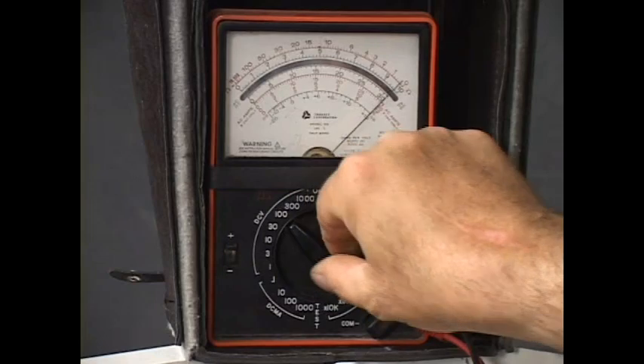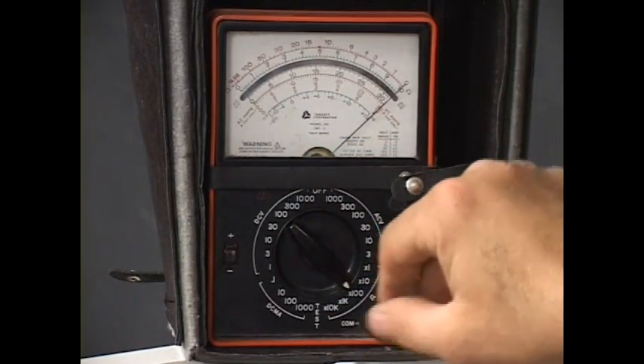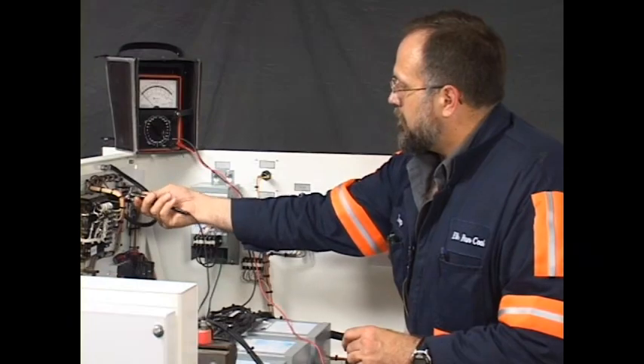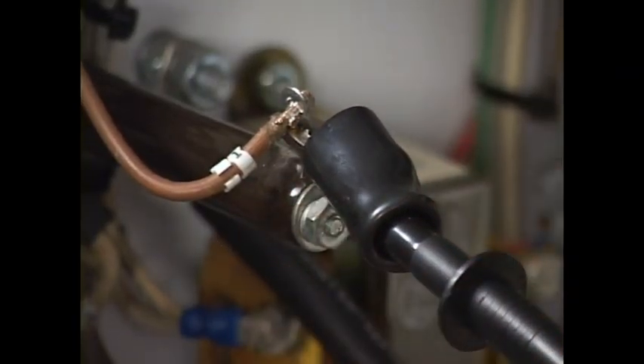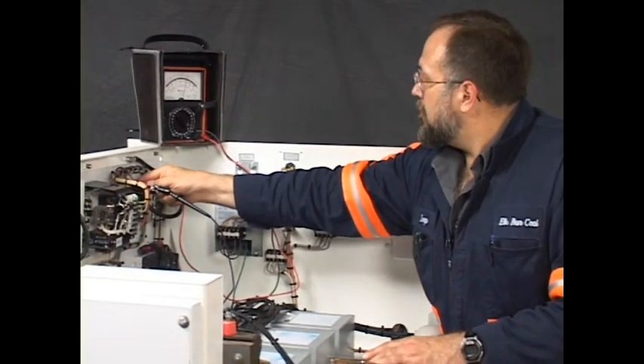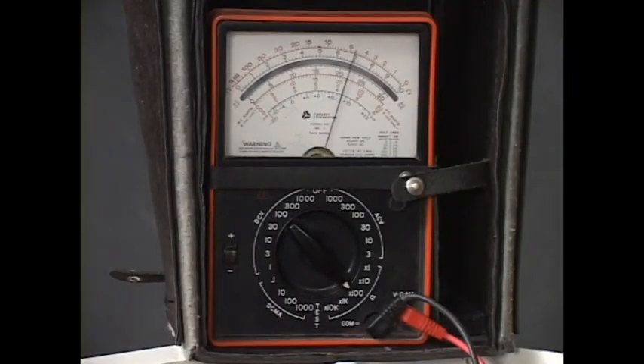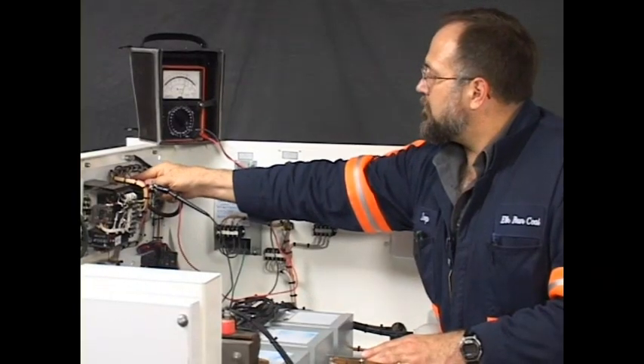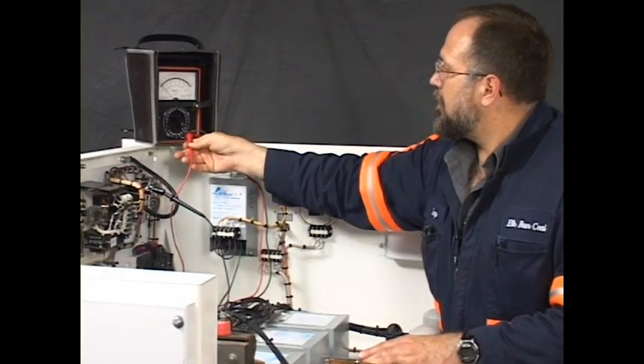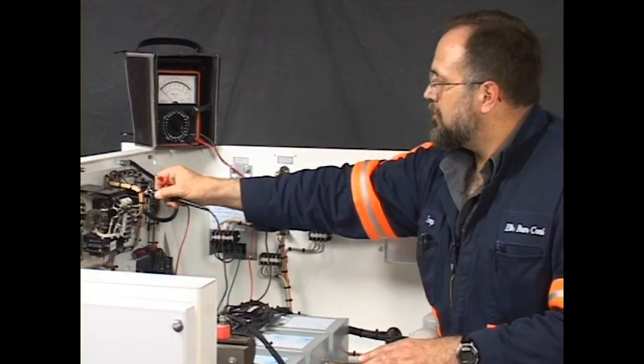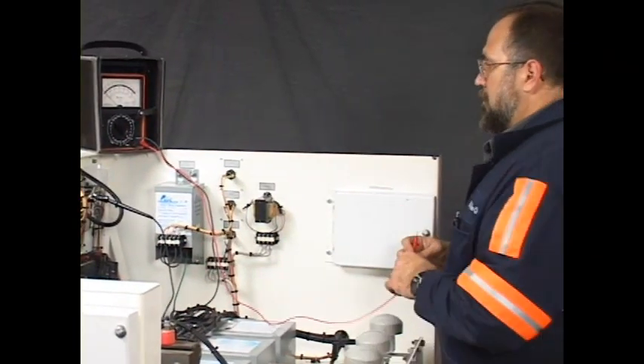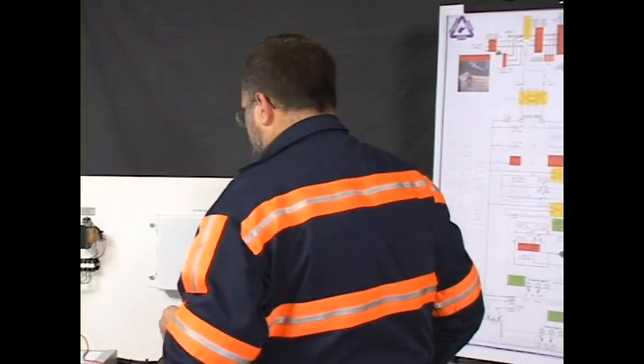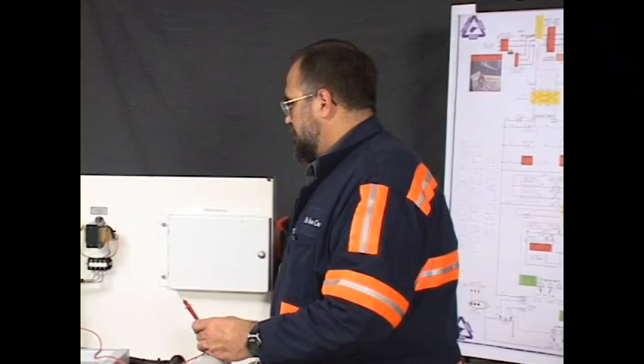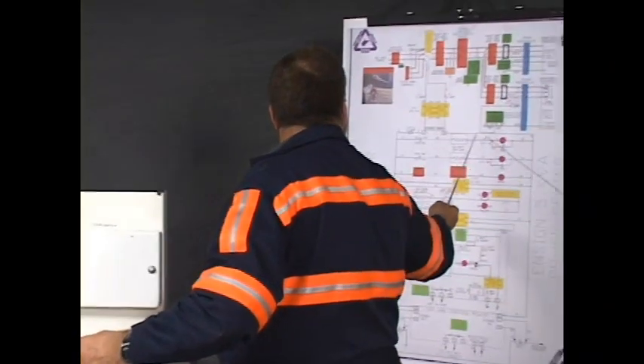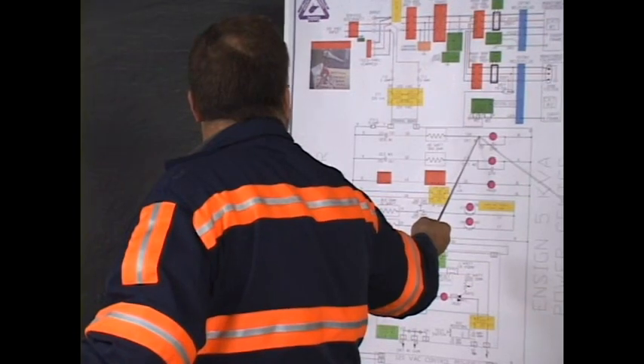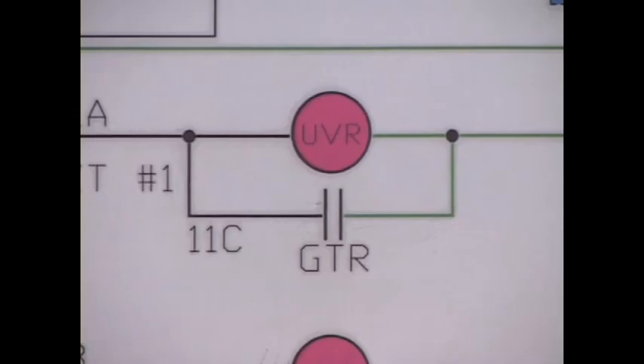I'm going to change my scale to the 100 scale. It stayed zeroed. I'm going to put the probe on one side and read this resistor. And as you can see, it reads very nearly exactly 5. 5 on the dial times 100, 500 ohms. So the resistor is good. We're going to proceed on wire number 11 from the load side of that resistor. From here, we're going to go to this terminal here, which is a little terminal block that powers the UVR and the GTR.